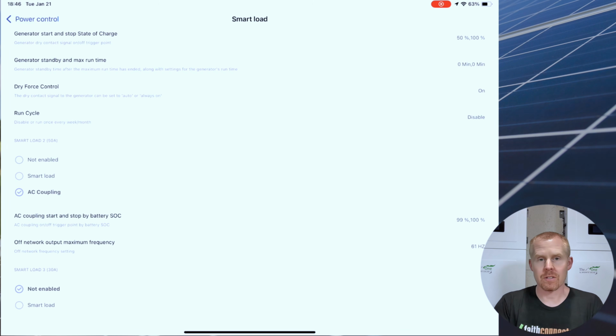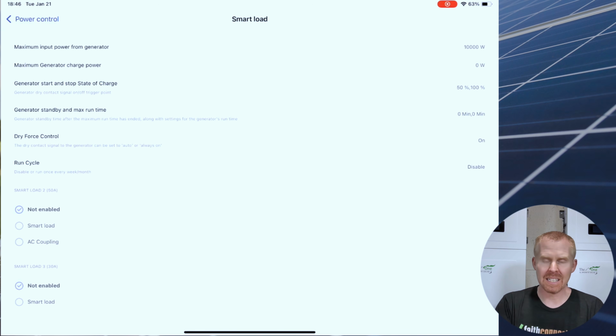AC coupling. So this is only available on the 50 amp breaker. You can see you can set a start and a stop state of charge. You have to use a dedicated PV inverter or a micro inverter, which allows for frequency shifting. And so this is going to control when this turns on and when this turns off. It needs to be able to shift the frequency of the PV inverter to tell it to stop sending excess power. And so you can program that frequency based on the specific PV inverter that you have. I believe the AC coupling option and maybe even the generator option need to be enabled when your inverter is in standby mode.